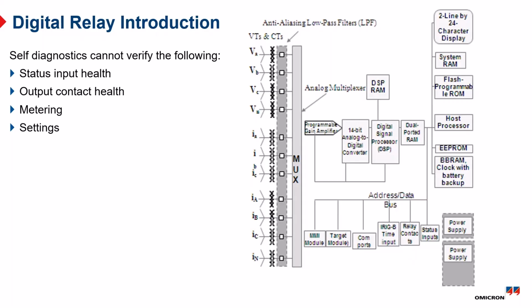Self-diagnostics cannot monitor the metering. So if there's a problem in this low pass filter, which is basically an LC filter, or in the magnetics in the bottom of the relay, we can't see it. And also, of course, self-diagnostics cannot verify that the settings are correct for the application.